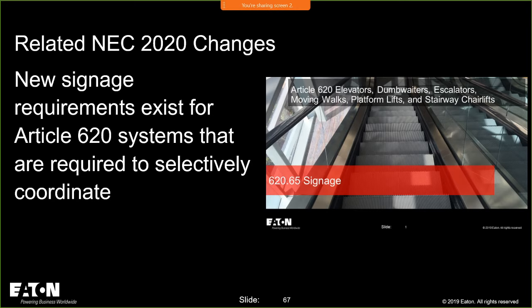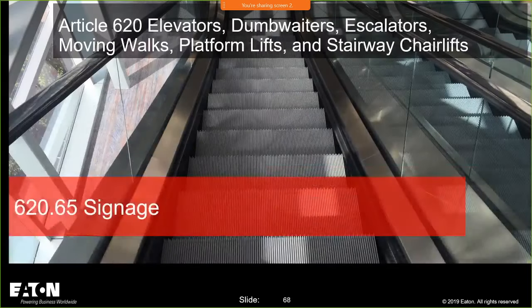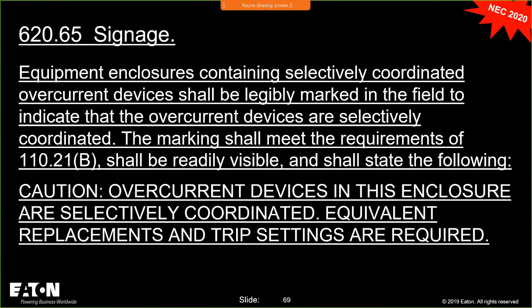Now, here's the difference that we made in the 2020. For the devices in these applications in 620.65, they added new language that basically says that when you have a system with devices that are selectively coordinated, we have to raise the awareness of maintenance individuals and anybody after the fact that those devices have been chosen for a specific purpose. And if there are set points on those devices, they are programmed with a specific purpose in mind. If we are going to replace a device in the field, it has to be selected and applied with that in mind.